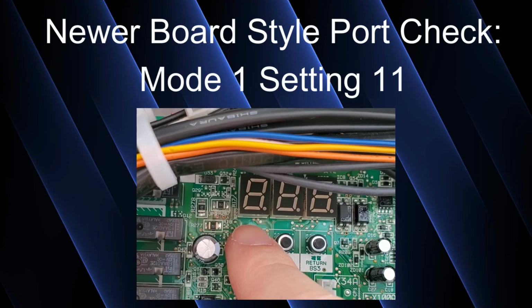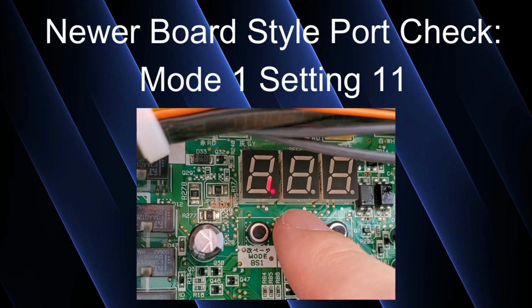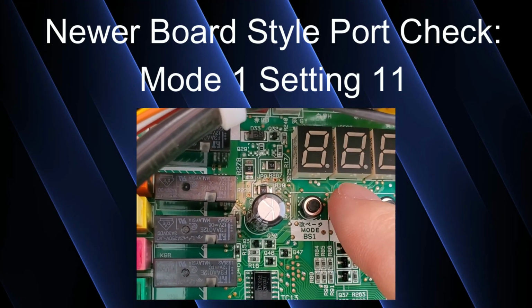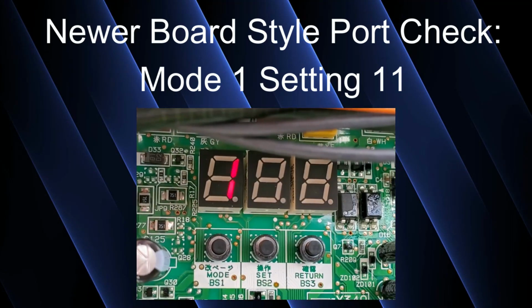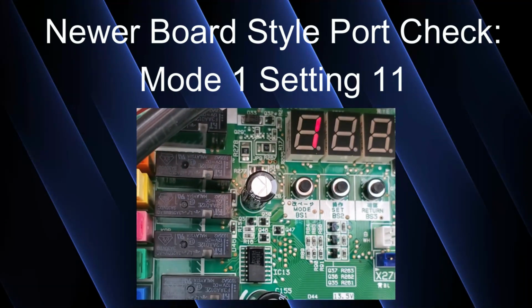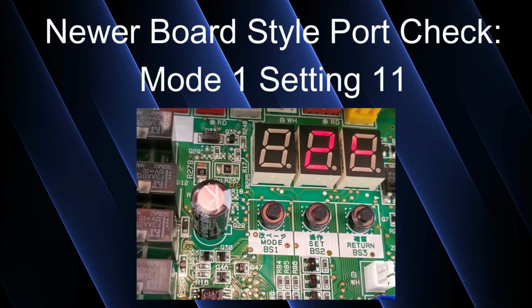On the newer boards, the ones that have that digital readout, press mode one time, the screen flashes 1.00. Now you're going to press set 11 times, 1.11, and then press return once, and it will simply give you the number of ports that it sees. So again, if you're using 7, hopefully it flashes a 7 on screen.